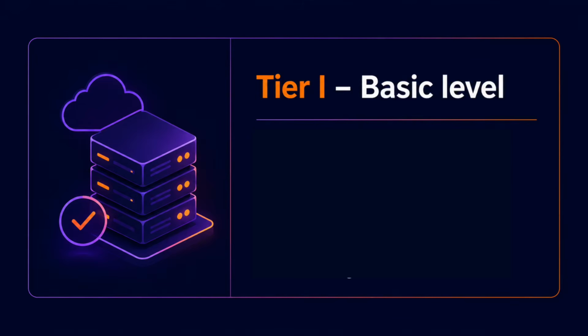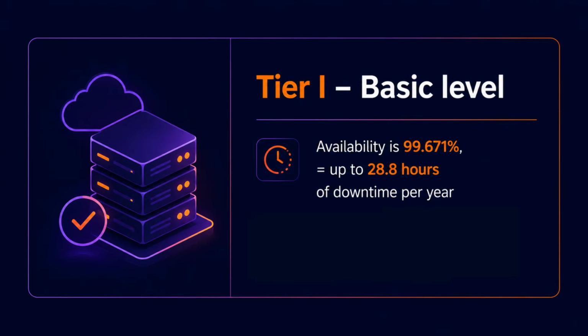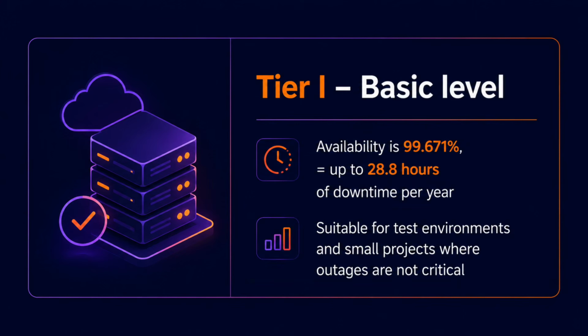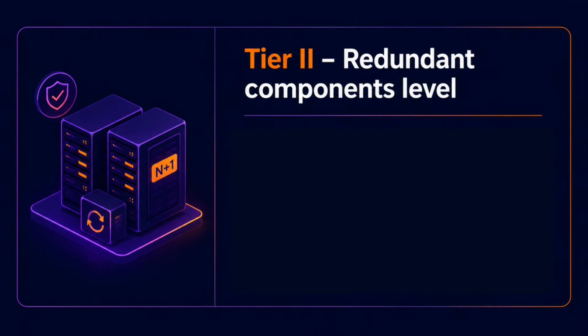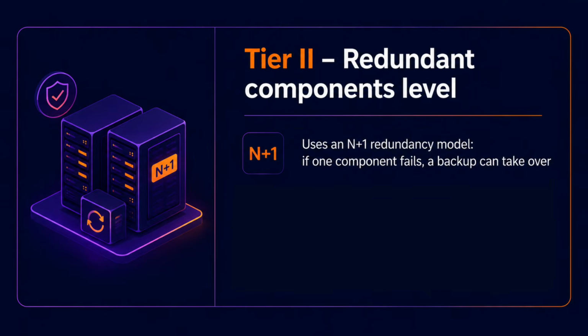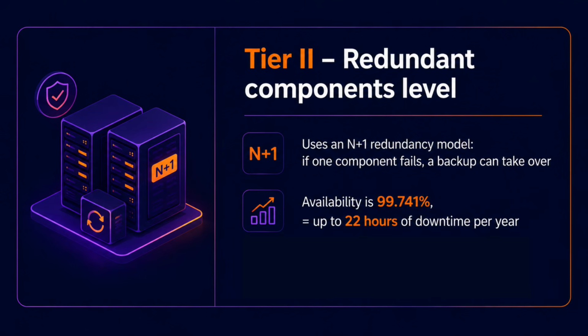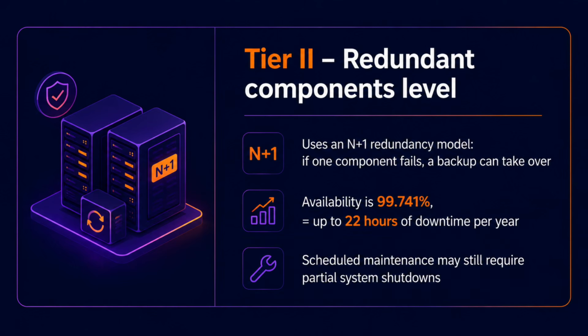Tier 1, basic level: a single path for power and cooling with no redundancy of critical components. Availability is 99.671%, which equals up to 28.8 hours of downtime per year. Suitable for test environments and small projects where outages are not critical. Tier 2, redundant components level, uses an N+1 redundancy model. If one component fails, a backup can take over. Availability is 99.741%, around 22 hours of downtime per year. However, scheduled maintenance may still require partial system shutdowns.